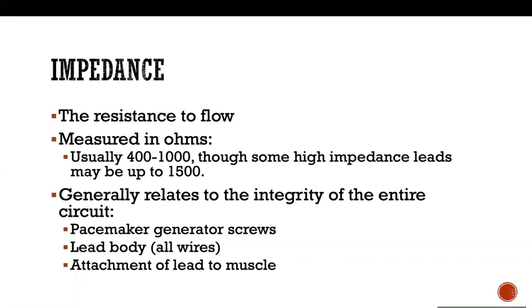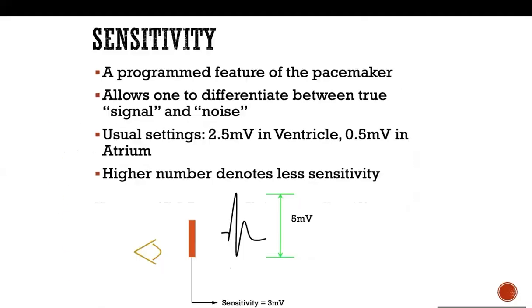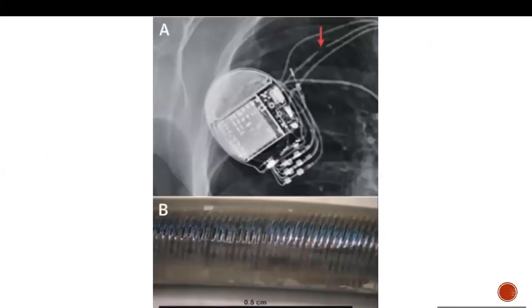So what does the lead contain? We said there are the wires inside and the silicone wrapping outside, the insulation. So if the silicone wrapping outside is broken, then there is nothing to keep the resistance inside. So there's going to be a lot of leak of energy, so there's not going to be a lot of resistance.